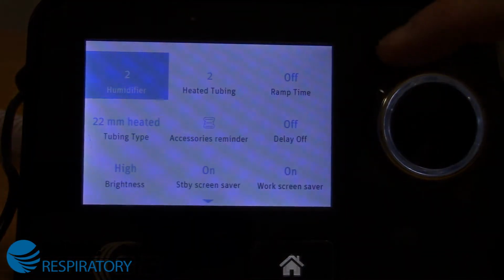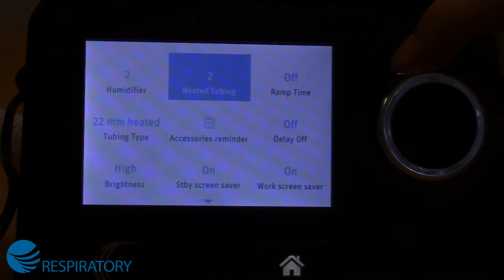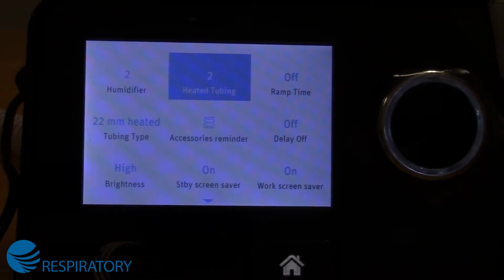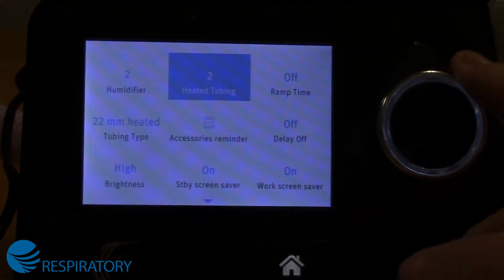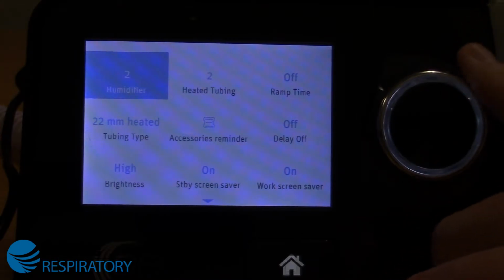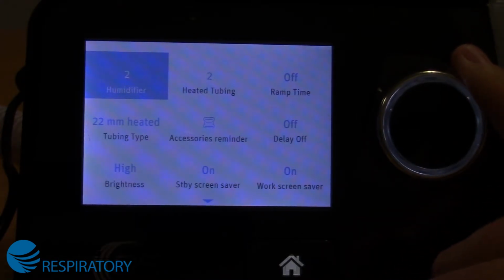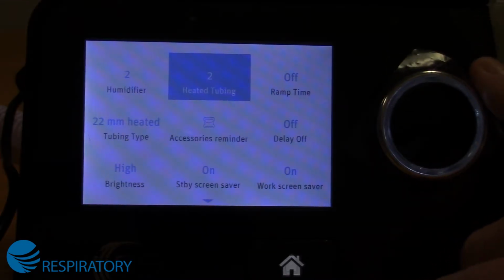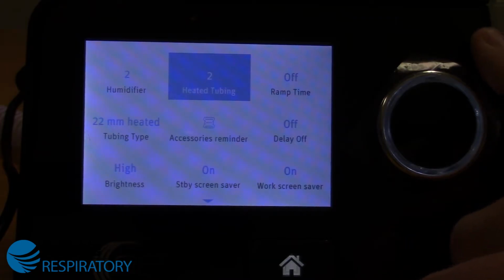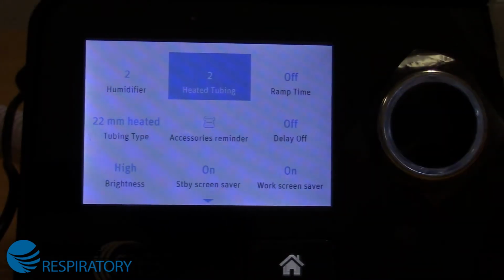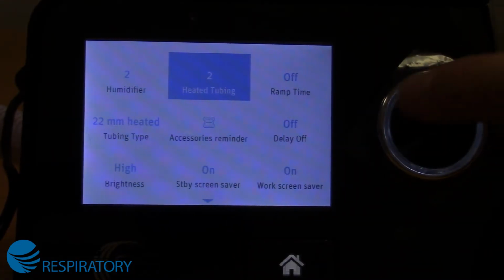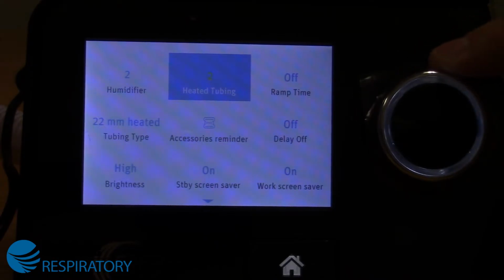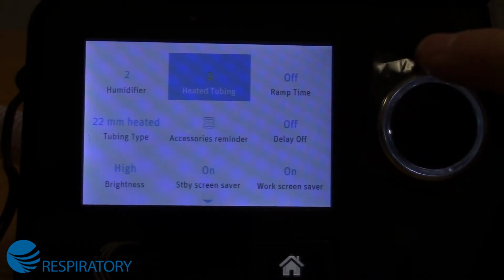The key difference to understand is that the heated tubing's sole purpose is to help minimize any condensation inside of your tube. We recommend starting them together at the same value and adjusting accordingly, whereas if you are still very dry, that's an indication to increase the humidity level. If you liked the humidity level, but you found there was a lot of moisture in the hose, then that would be an indication to specifically increase the heated tube setting. And that is simply by pushing the dial in to access, changing the value, and then clicking again to confirm.